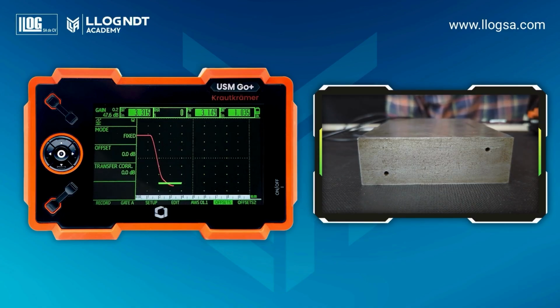To do this, select Customize in the Mode function and create 2 additional curves. We customize the sensitivity level of the first additional curve to 50%, that is, -6 decibels, which represents a discontinuity half the size of the reference level.